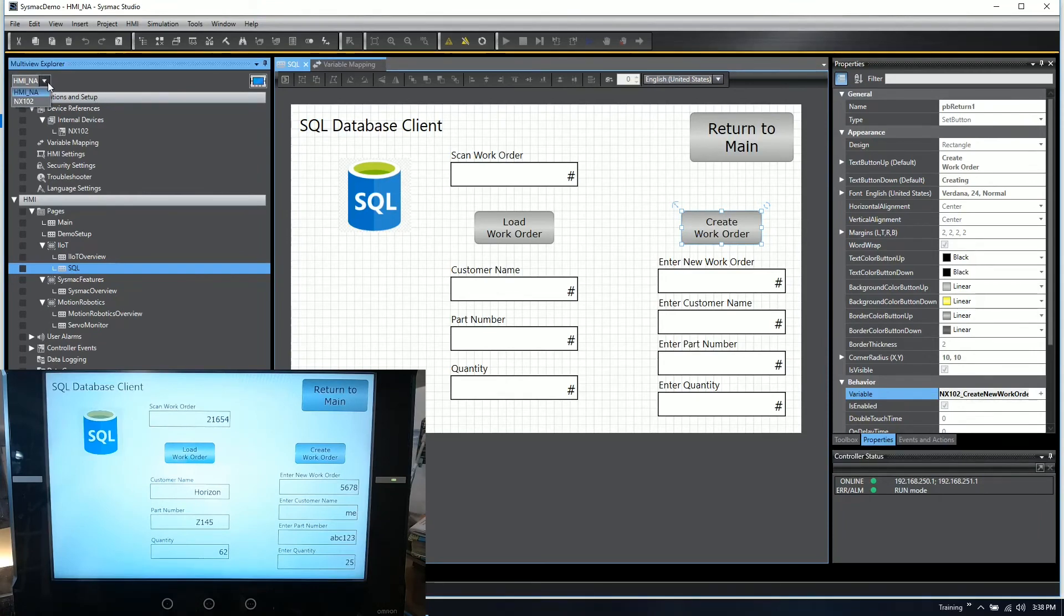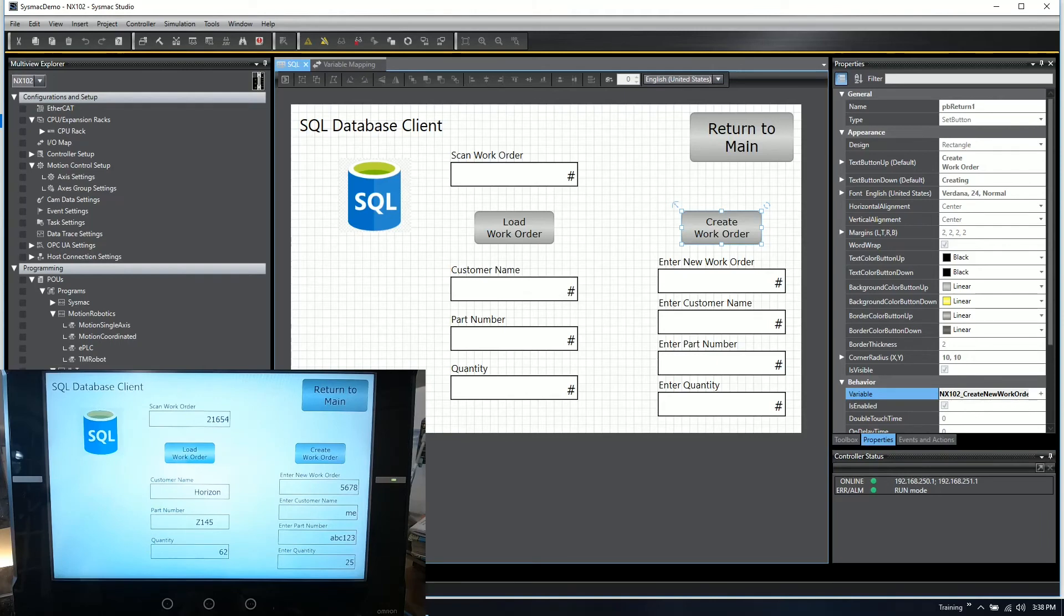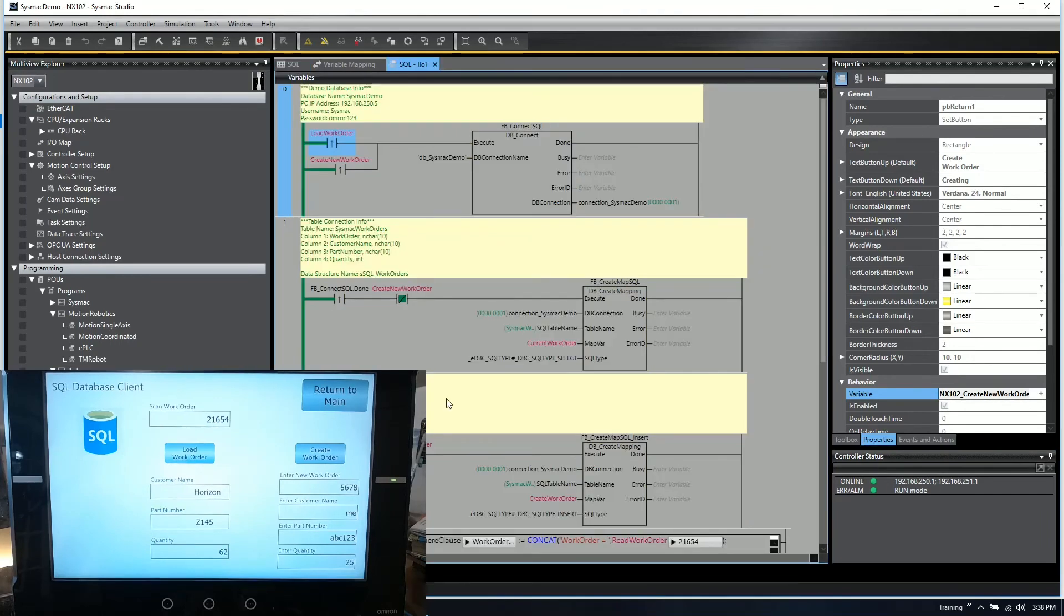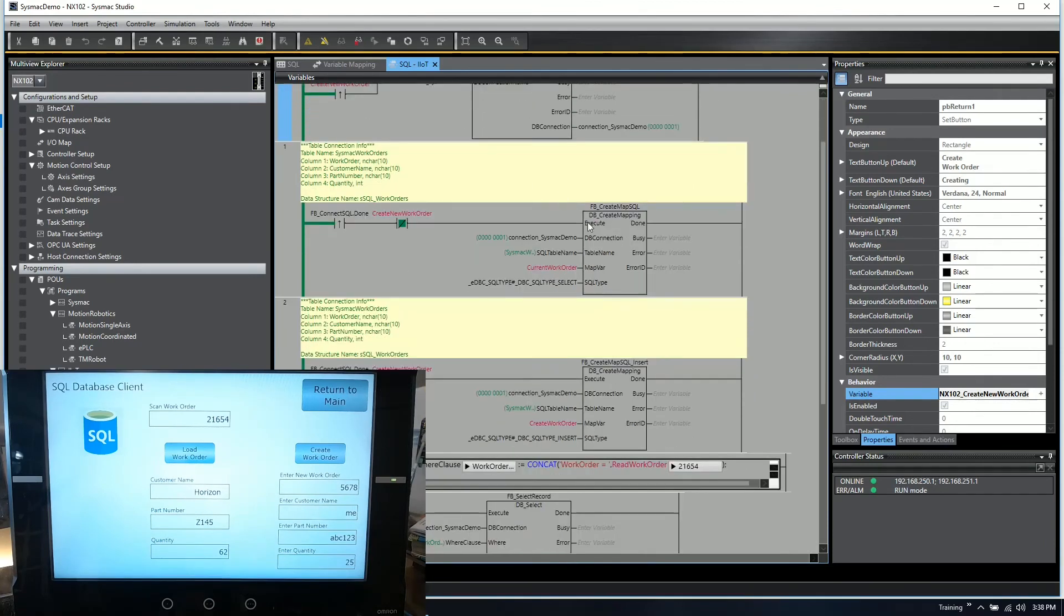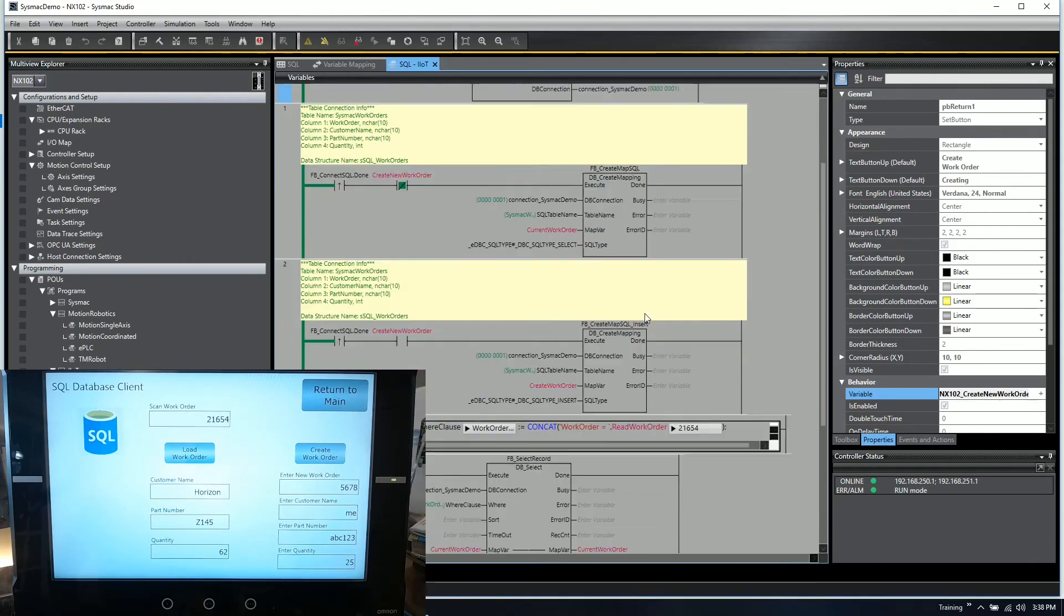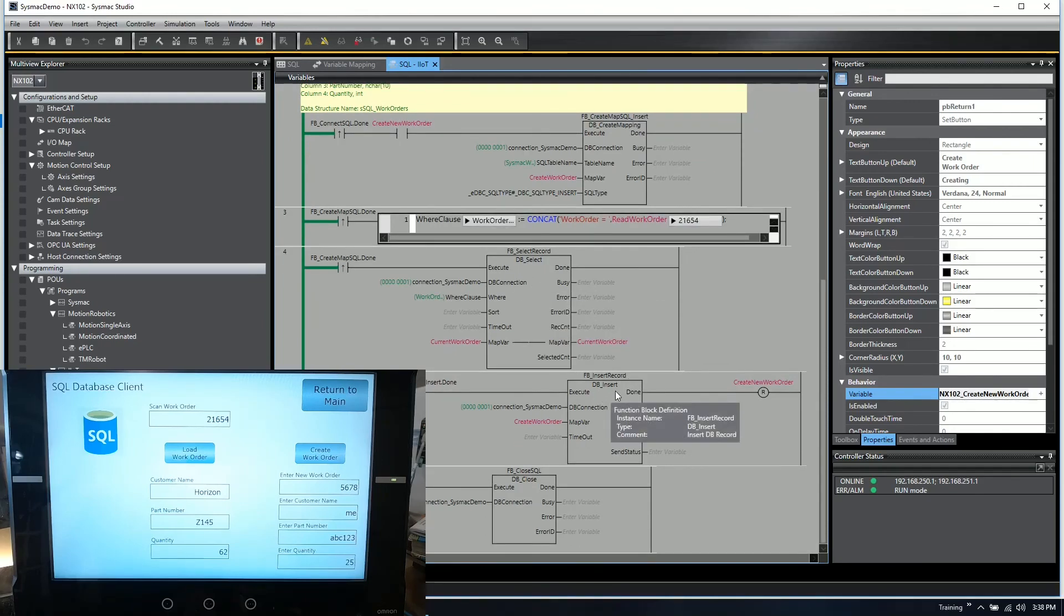How all of that is done is through a few function blocks inside of SysMac Studio. After you create the connection, there is a database connect function block which connects from the PLC to the SQL database. Then we can do some variable mapping so we can create variables that match the table columns on the SQL database. And then we have a function block to read, which is called dbselect, or to write, dbinsert. And then once those are done, we simply do a database close.